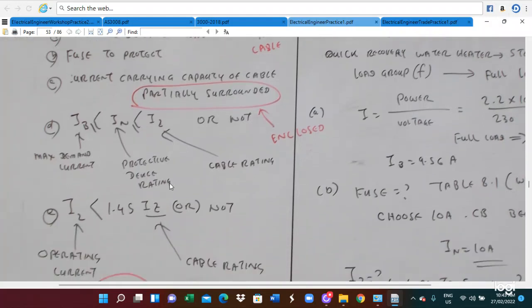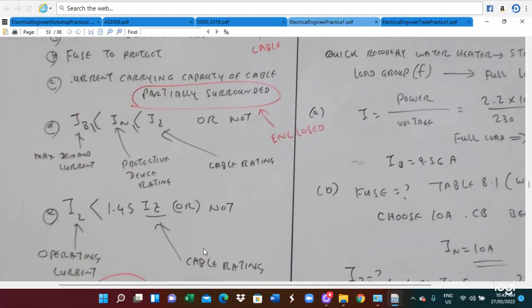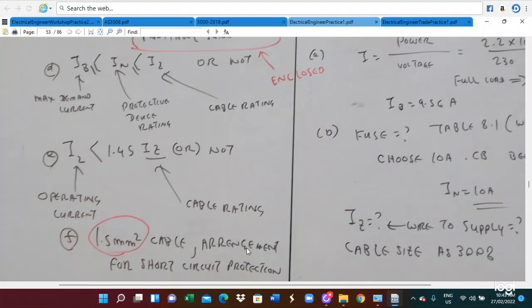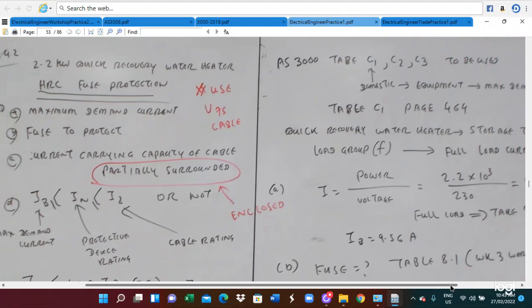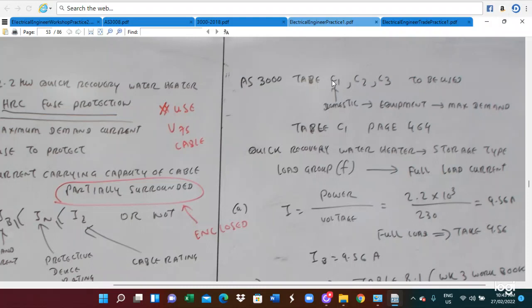The first condition is IB ≤ IN ≤ IZ. The second condition involves the operating current. For the protective device rating, we need to utilize the cable. We have to use a V75 cable. To find the maximum demand current, we use Table C1, C2, or C3 of AS3000. For a domestic installation, we use Table C1.